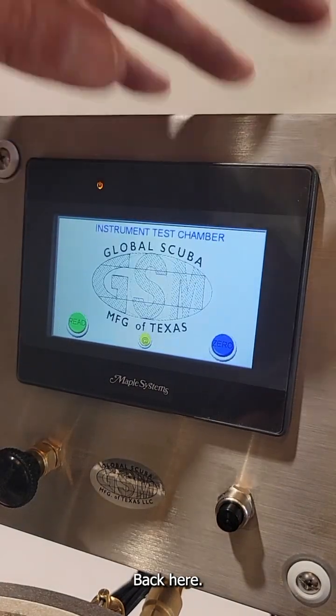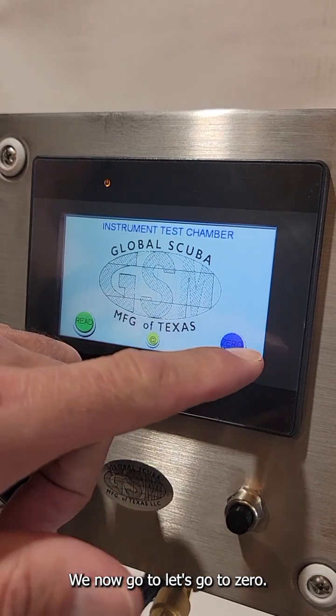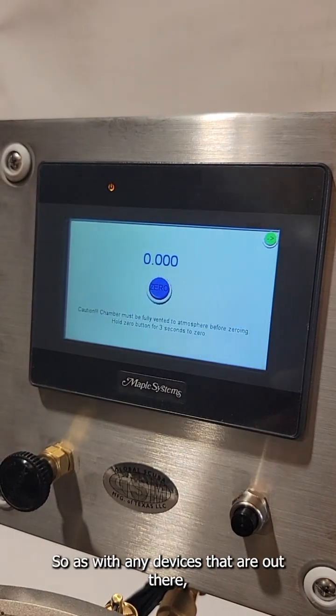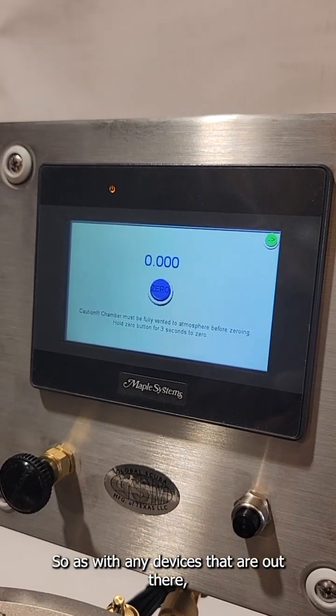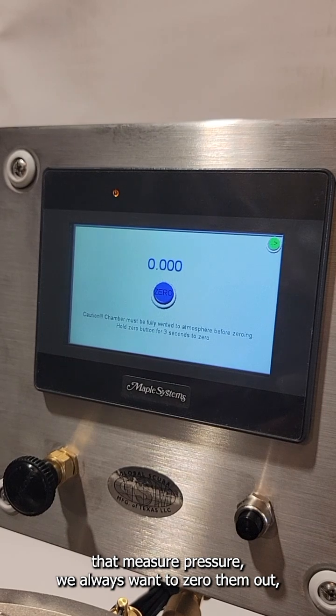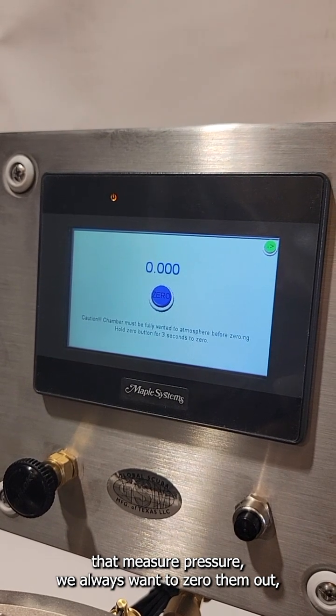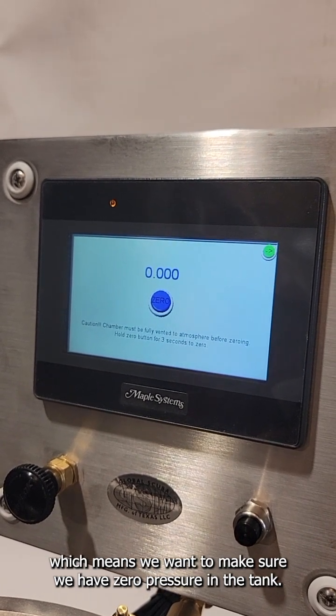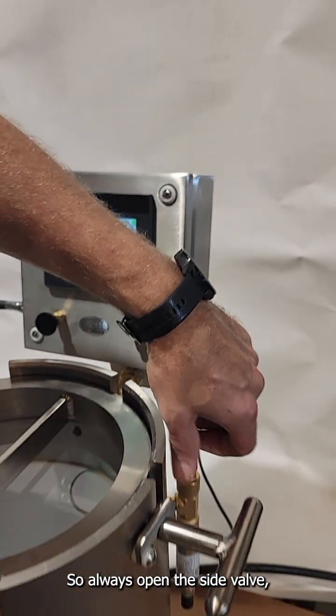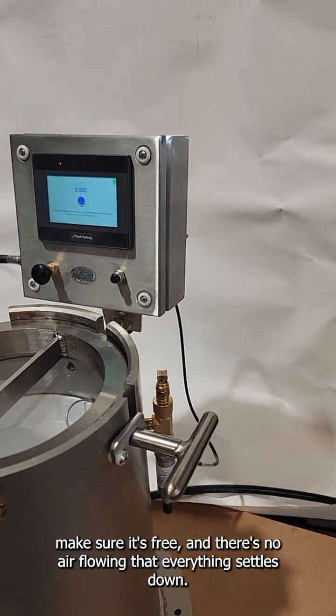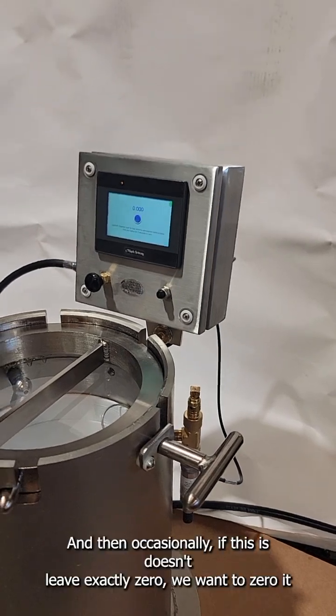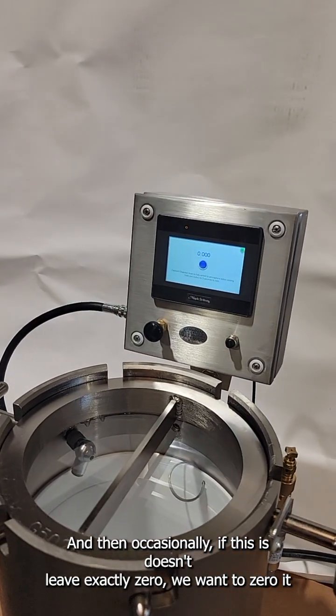So going back here, let's go to zero. As with any device that measures pressure, we always want to zero it out, which means we want to make sure we have zero pressure in the tank. So always open the side valve, make sure it's free and there's no air flowing, and that everything settles down. Then, if this doesn't read exactly zero, we want to zero it.